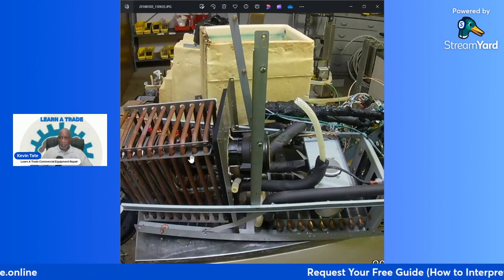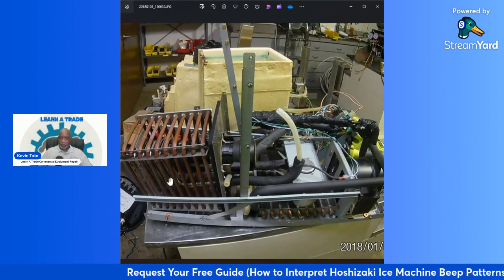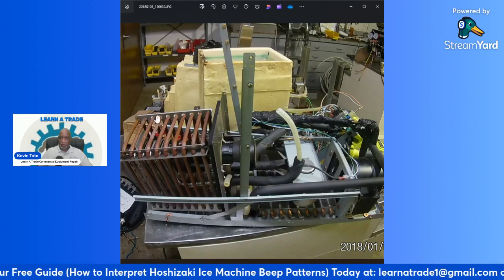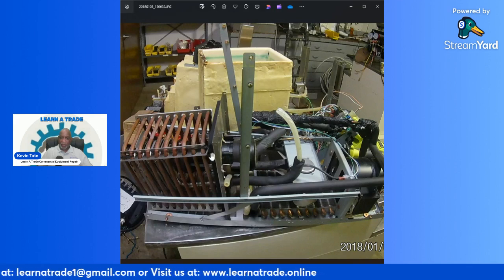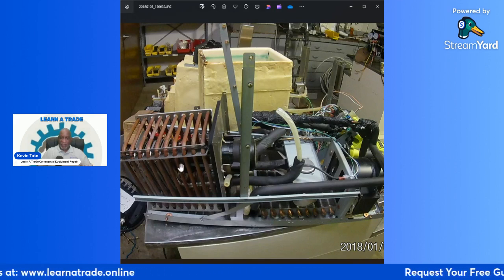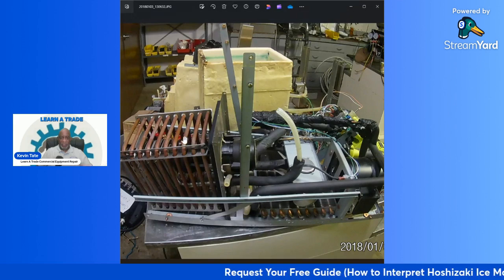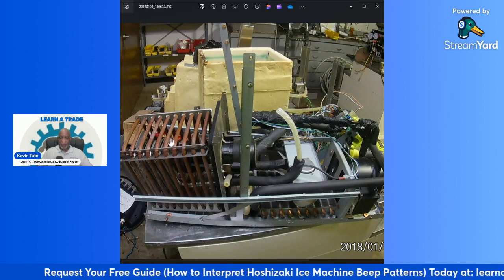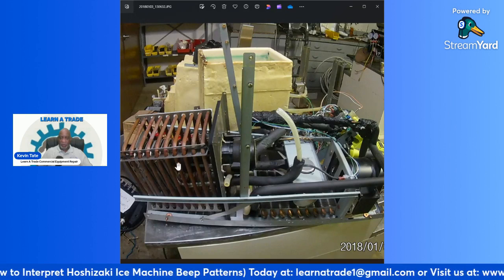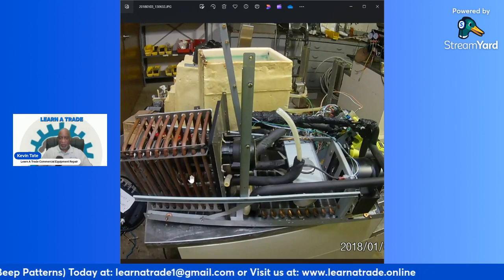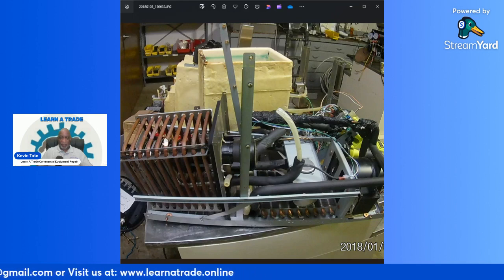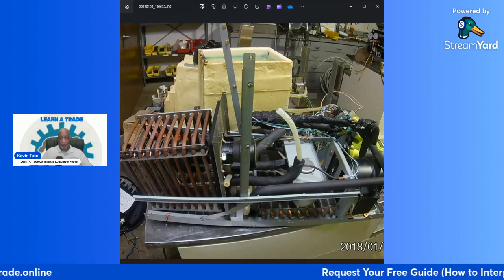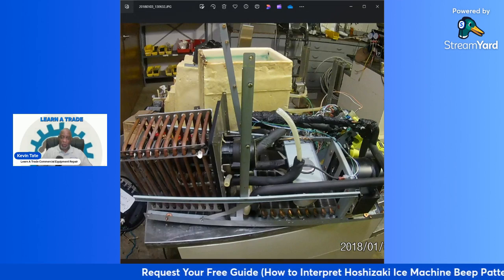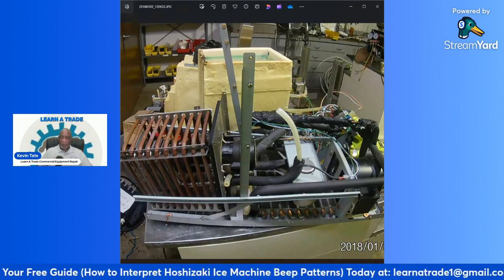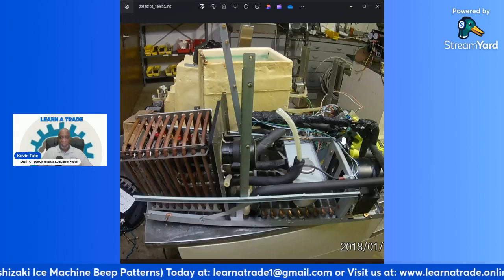Like I was explaining earlier, this may help you. These are the refrigeration coils. The water is submerged into this water bath, and this pump circulates that water around so it's not stagnant, and then it doesn't freeze solid, but it does freeze. The refrigeration is going through these lines and freezes the water it's submerged in, and this pump keeps that water circulating. So there's like a wall of ice around this, and in the center the water is in motion from this water pump, which pumps that cold water out of here and up through the upper evaporator, which is the cabinet area I've already taken off.